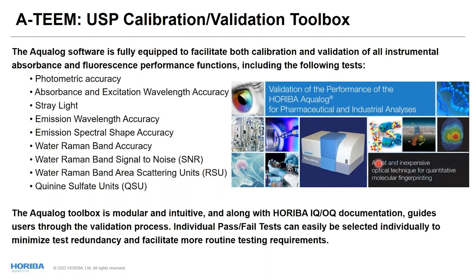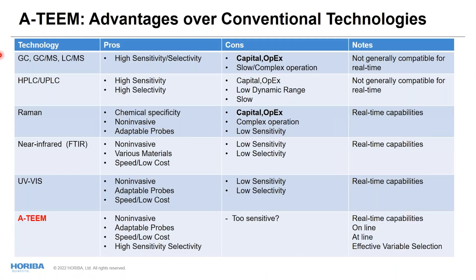The instrument is completely calibrated and certified to the latest US Pharmacopeia chapter guidelines for all aspects of absorption and fluorescence — wavelength accuracy, stray light, signal-to-noise, and more. This makes it well-suited for quality control applications in almost any laboratory requiring these types of regulations.